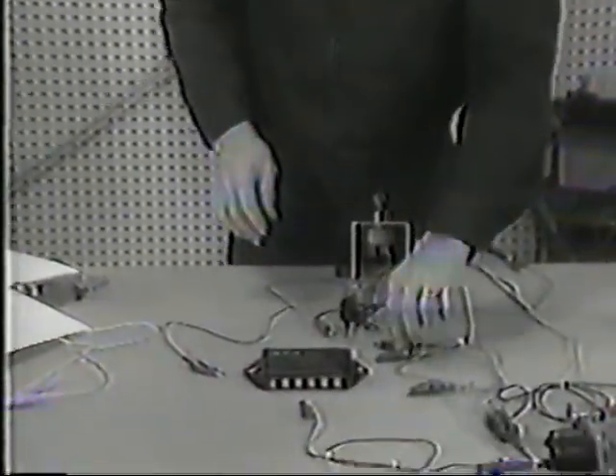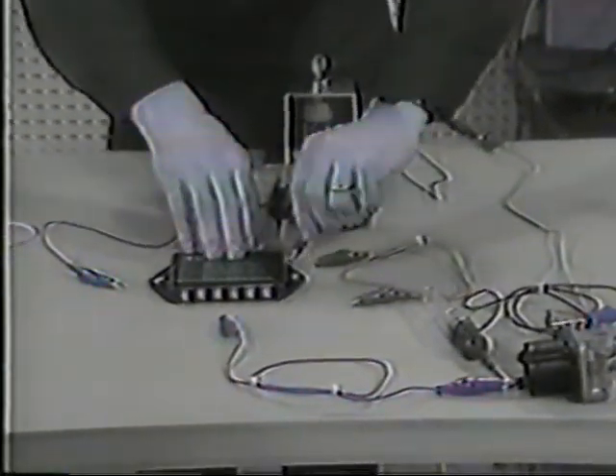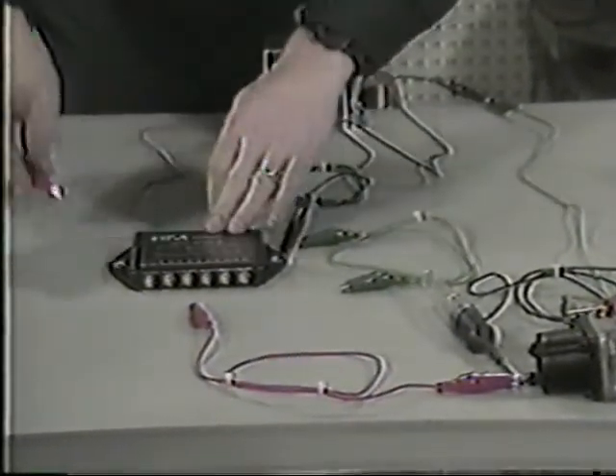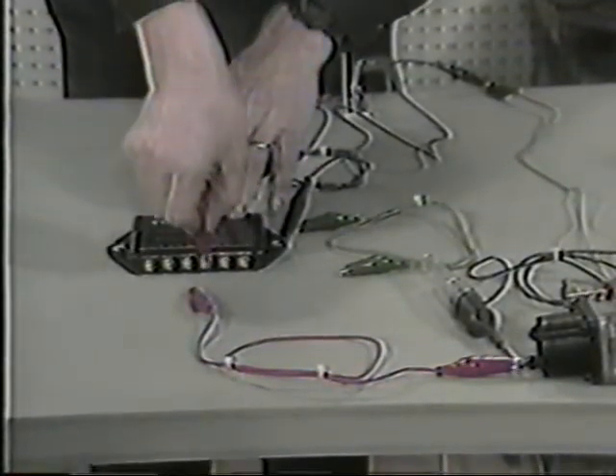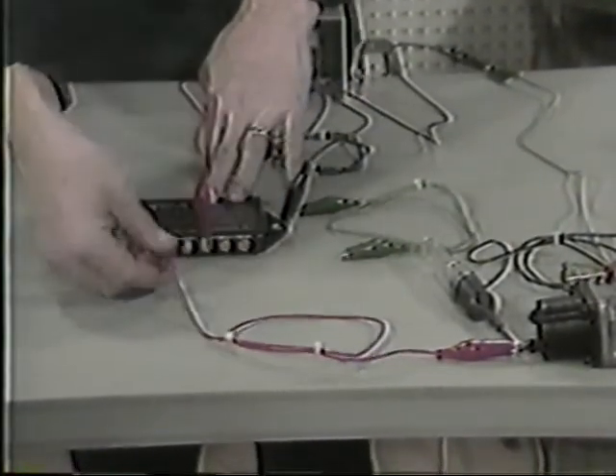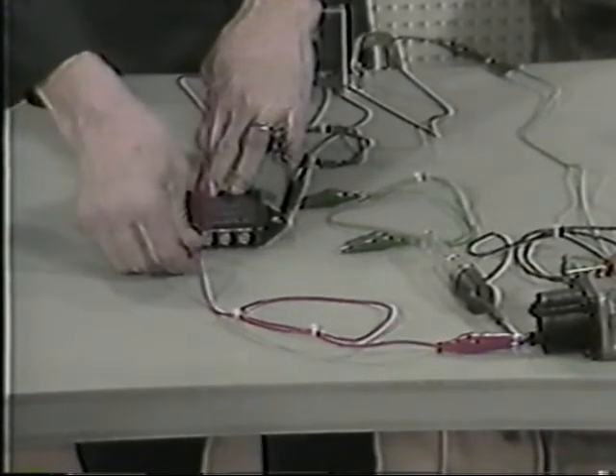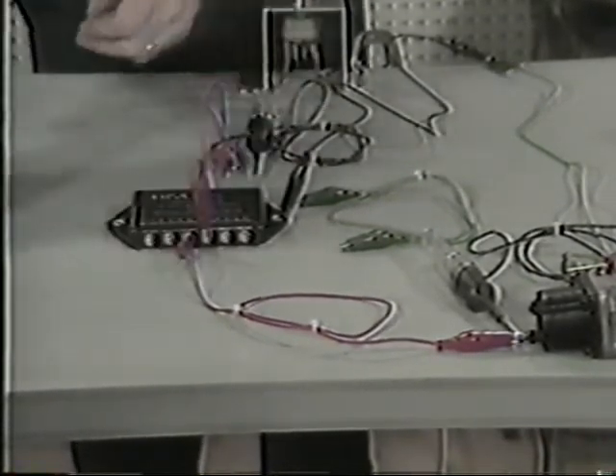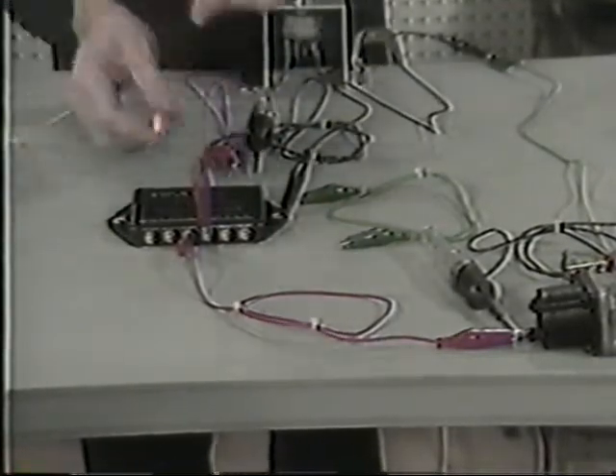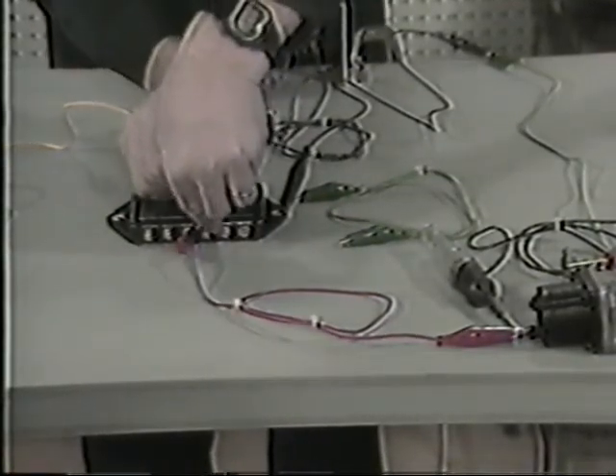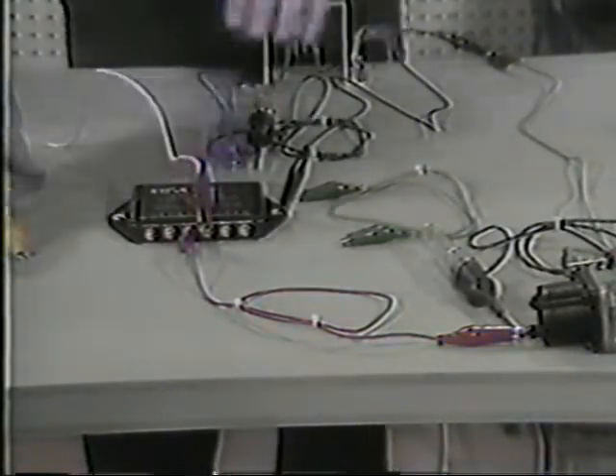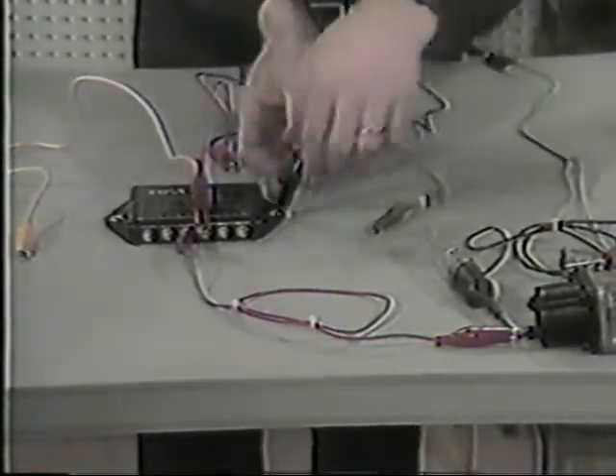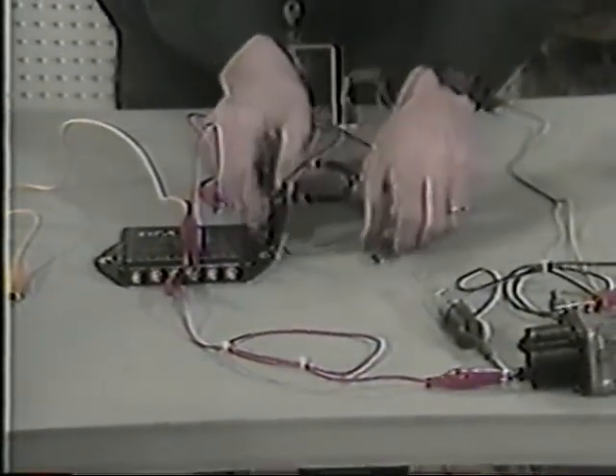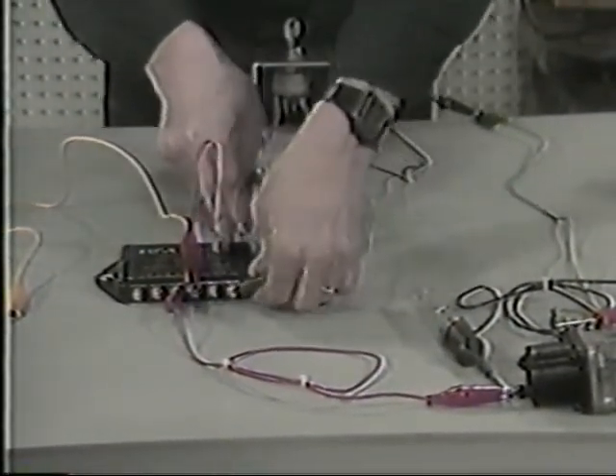Next, let's bench test the 9031 alarm and shutdown module. Begin by connecting one of the module mounting ears to ground. Connect your key switch voltage source to terminal number 4. Connect the fuel solenoid test load to terminal number 3. Connect another jumper wire to terminal number 4, but don't connect the other end at this time. Connect a jumper wire between ground at the module ear and terminal number 6.